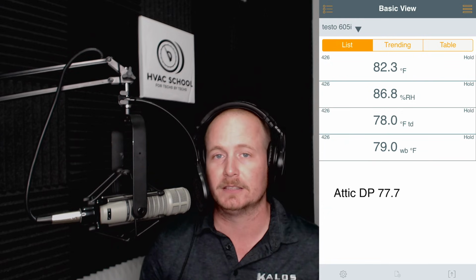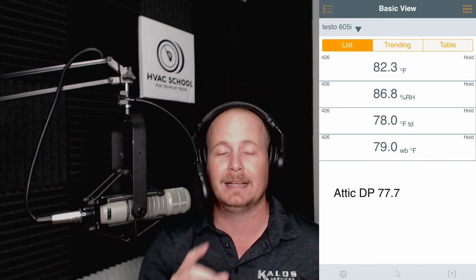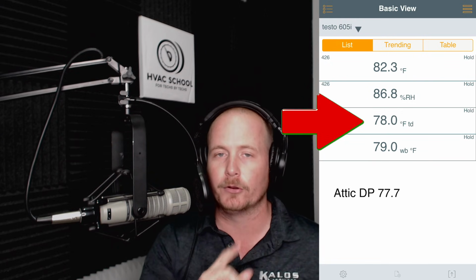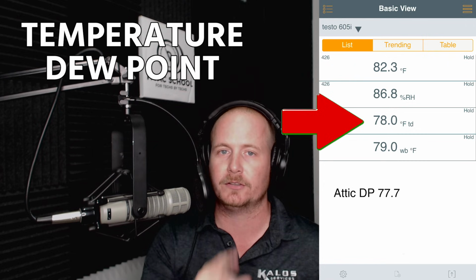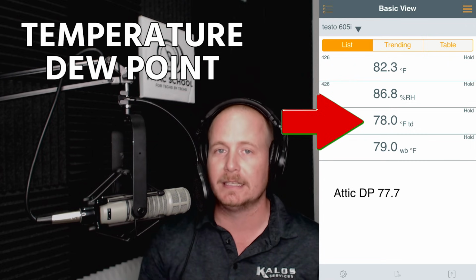That's a great psychrometer. You can use the Fieldpiece app or the Measure Quick app in order to get relative humidity, wet bulb, and dew point. You can also use the Testo 605i. If you're using the Testo app, as shown in this screenshot here, it says TD, and a lot of people don't know what that is. That is temperature dew point. So that TD means dew point. So that's an easy way for you to do it.